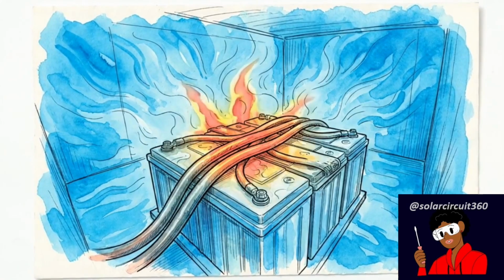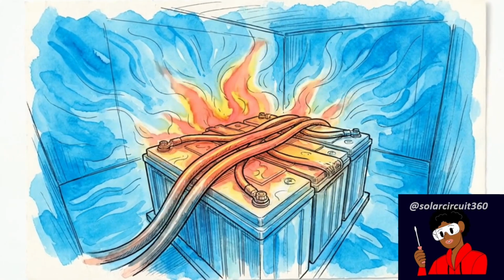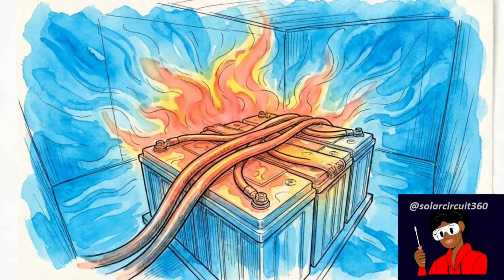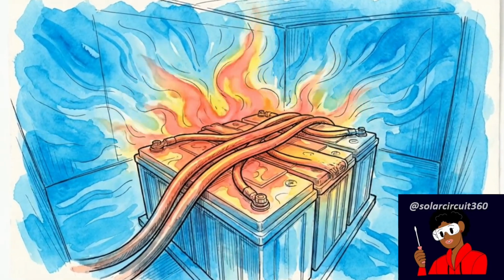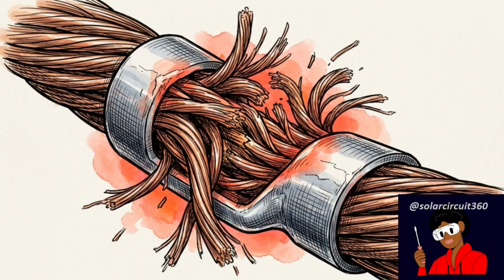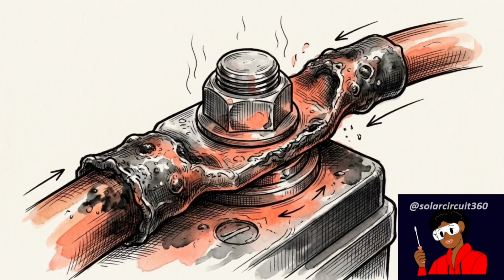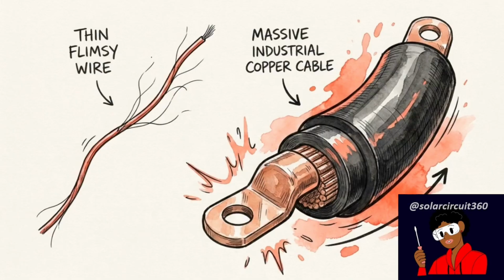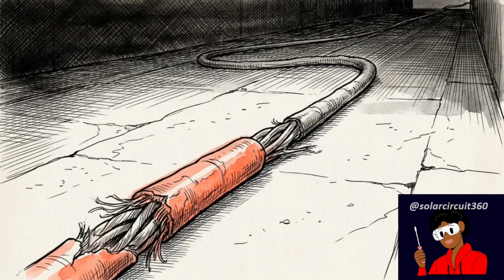Pushing hundreds of amps at low voltage generates extreme heat, causes energy loss, and puts heavy stress on the internal battery cell connections. Failing to step up the system's DC voltage architecture forces the battery into a physical bottleneck. It has to supply exponentially higher amperage, leading to inevitable failure under heavy loads. That extreme DC current demand interacts directly with the physical wiring, especially if the battery cables are undersized. High resistance in a cable creates voltage drop. The electrical pressure physically decreases as it travels from the battery to the inverter.